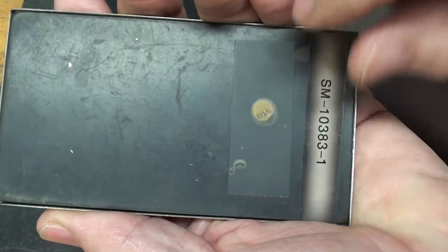Then looking at the next sample here, this is one that should read 19 micro inches. You can see there's an awful lot of scratches on that. That's for checking the stylus and notice the arrows there telling you which direction to run it, but this has been abused over many years.